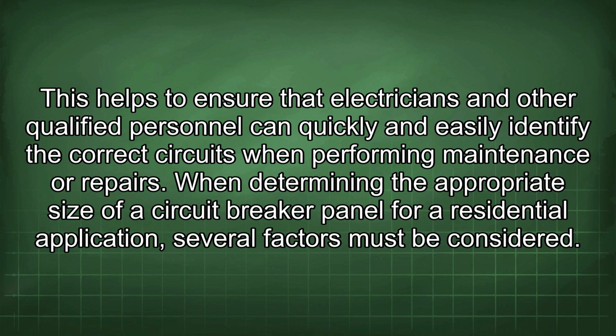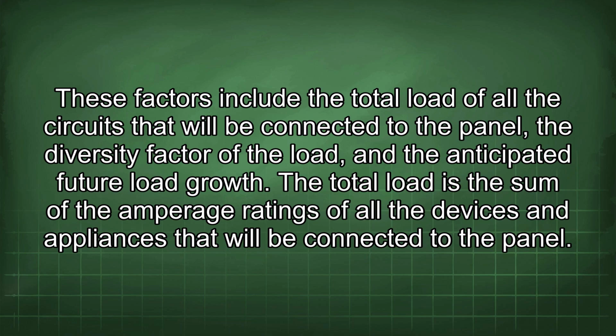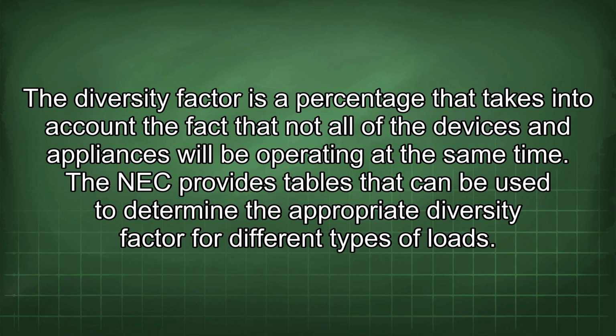When determining the appropriate size of a circuit breaker panel for a residential application, several factors must be considered. These factors include the total load of all the circuits that will be connected to the panel, the diversity factor of the load, and the anticipated future load growth. The total load is the sum of the amperage ratings of all the devices and appliances that will be connected to the panel. The diversity factor is a percentage that takes into account the fact that not all of the devices and appliances will be operating at the same time. The NEC provides tables that can be used to determine the appropriate diversity factor for different types of loads.